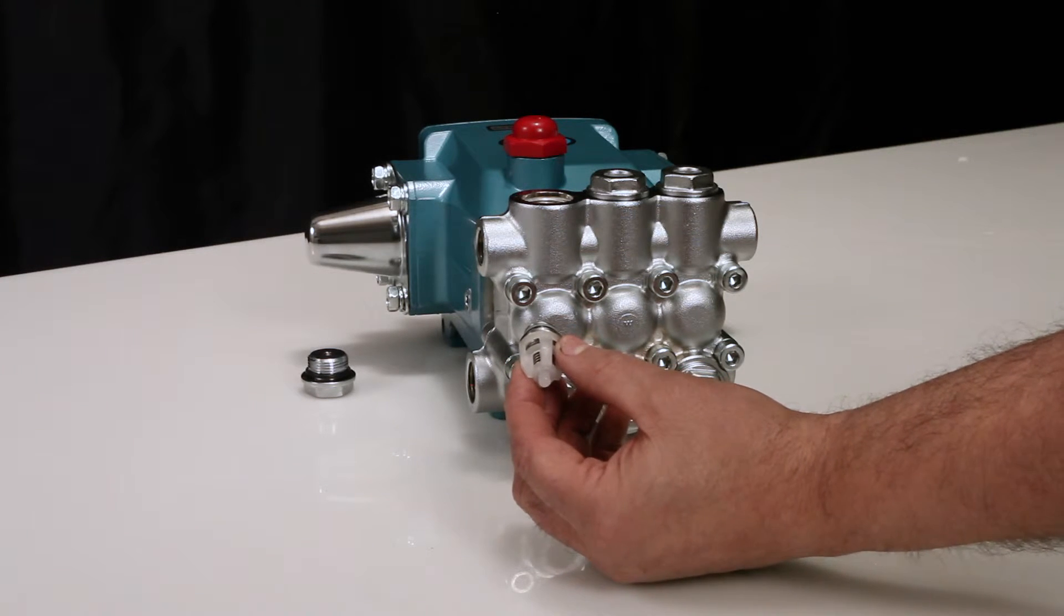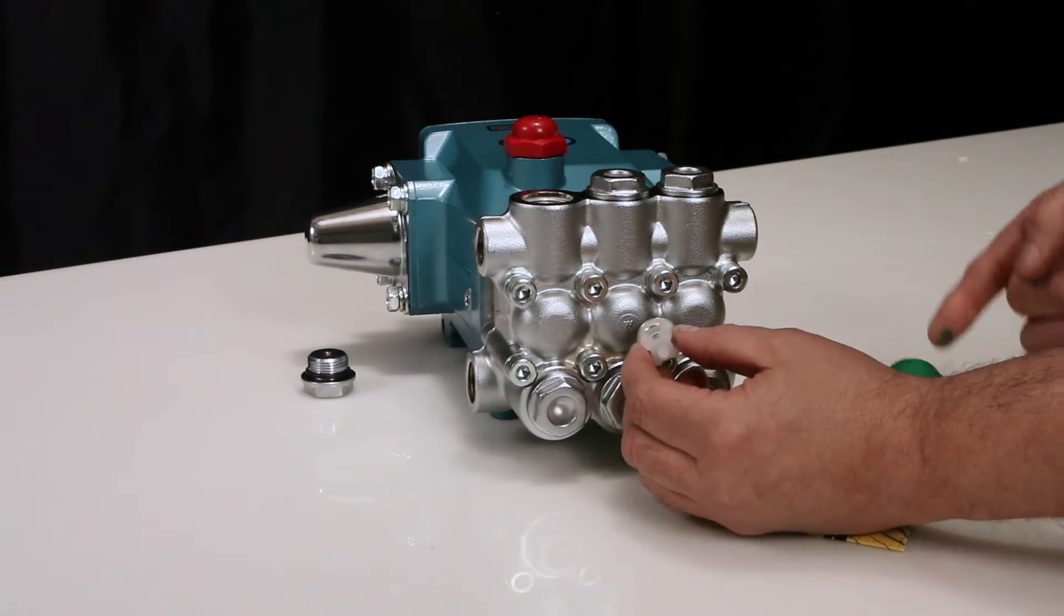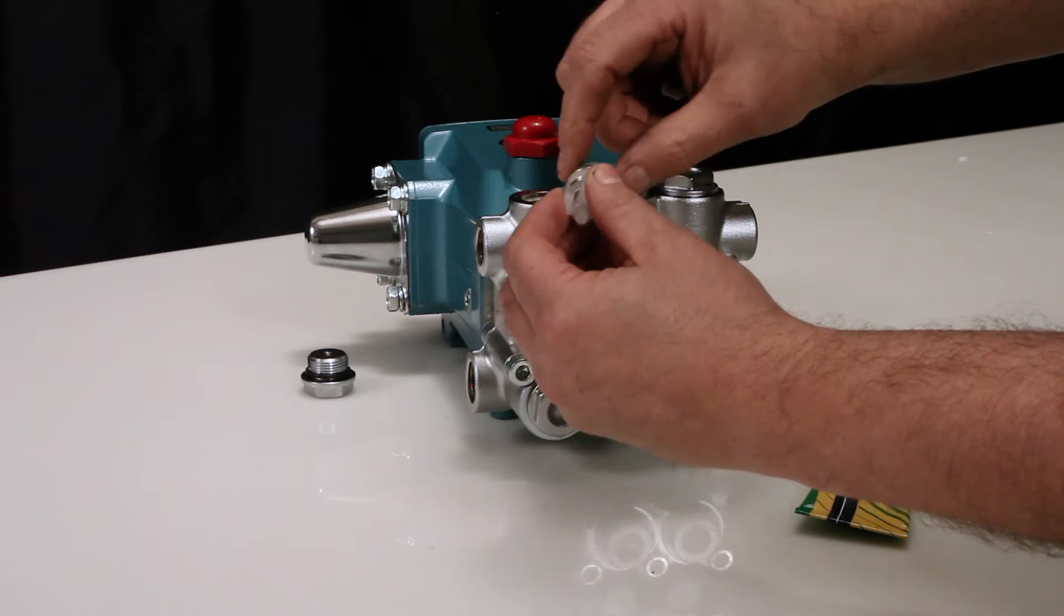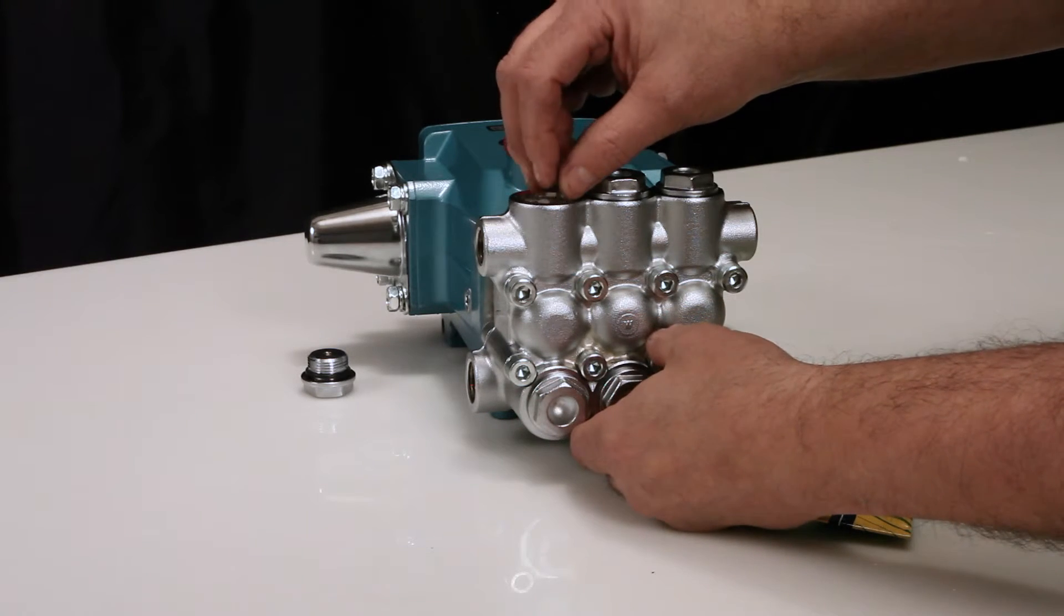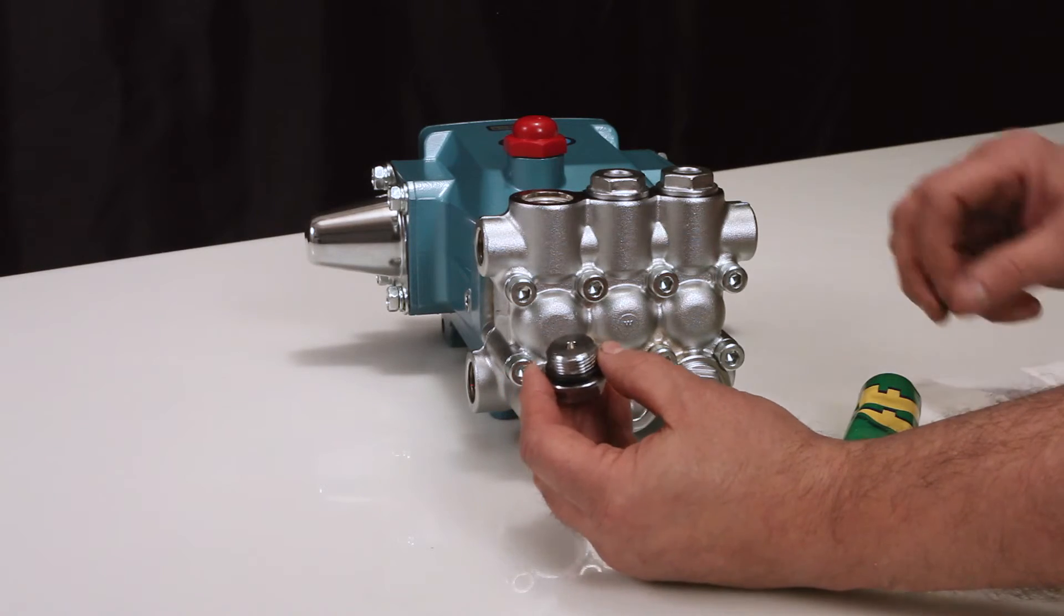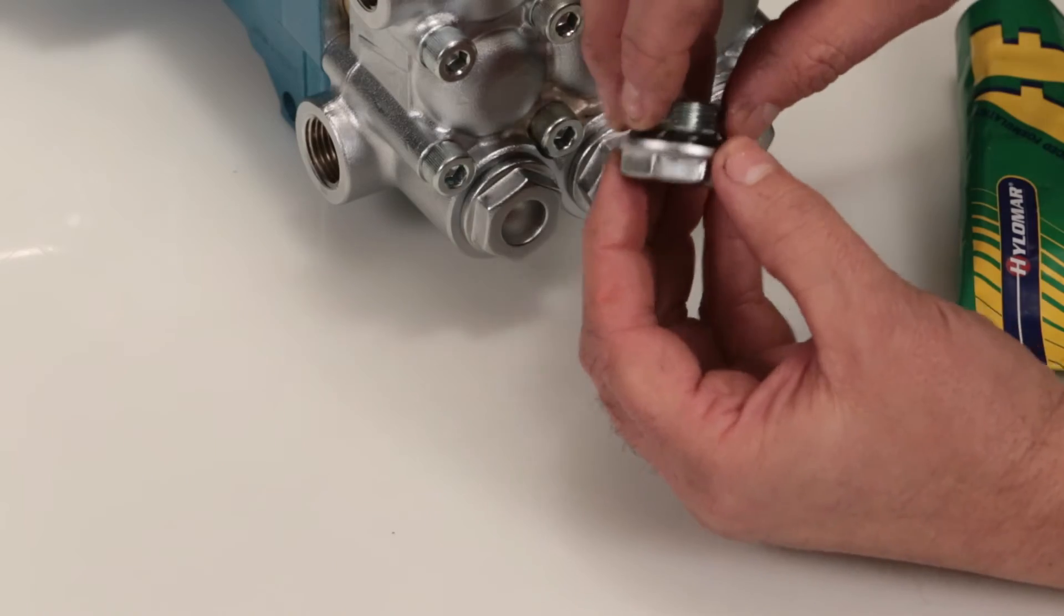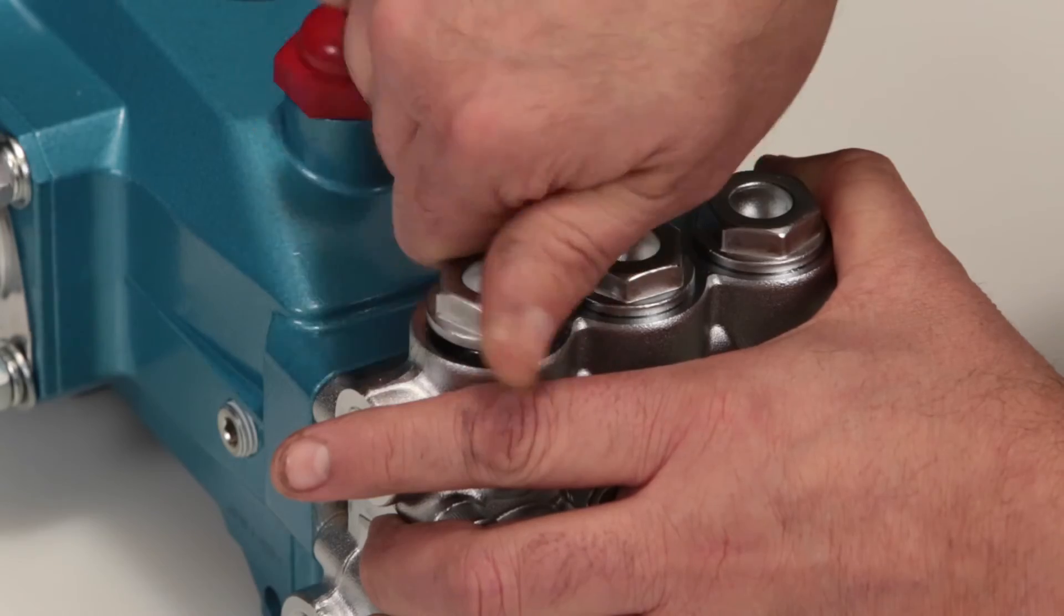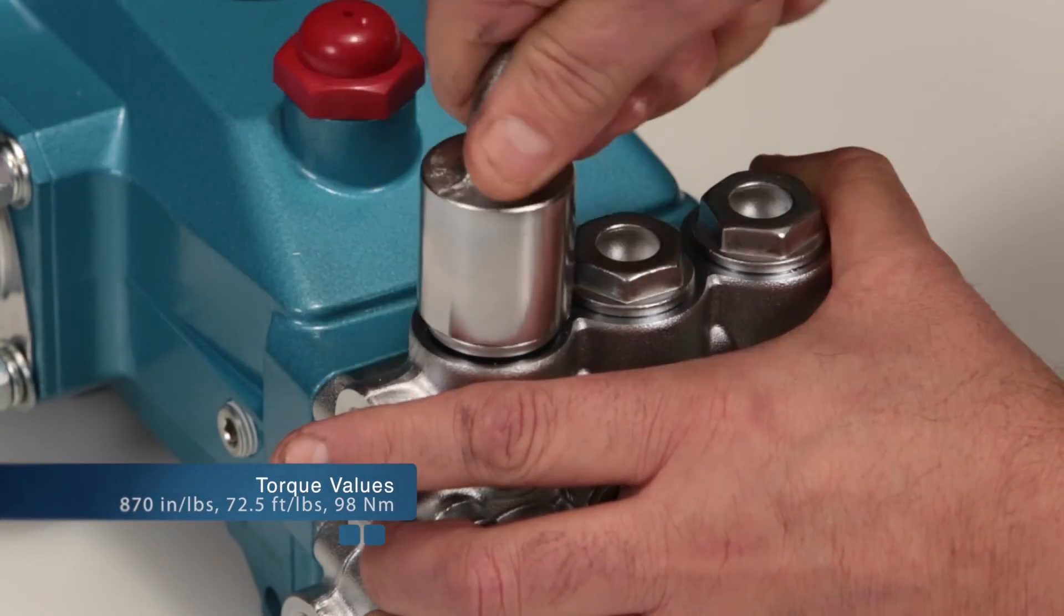Before reinstalling, lubricate O-ring and backup ring on valve assembly with liquid gasket. Next, insert valve assembly into manifold and press into place. Lubricate the O-ring and reinstall the valve plug. Torque to specification.